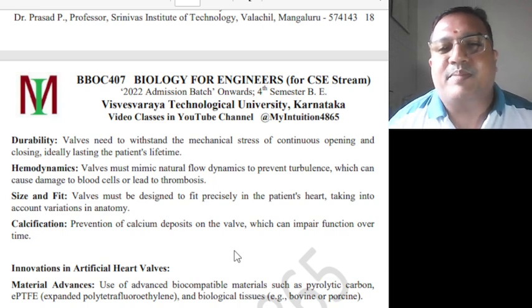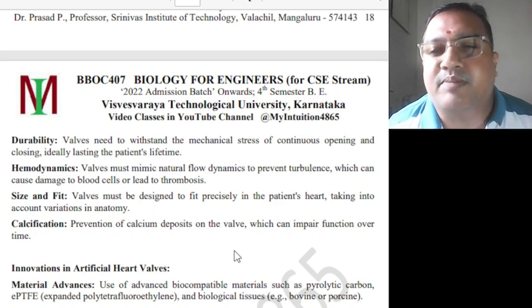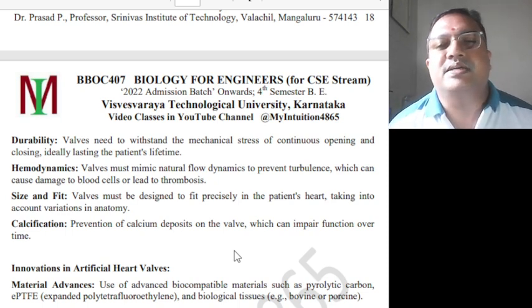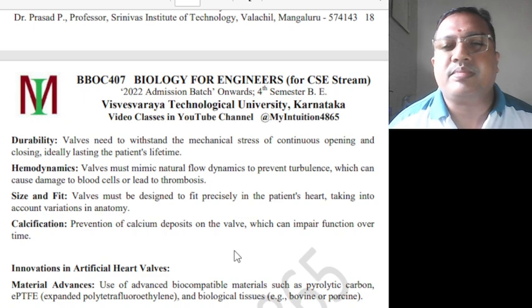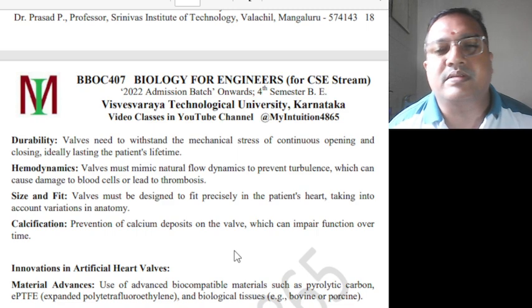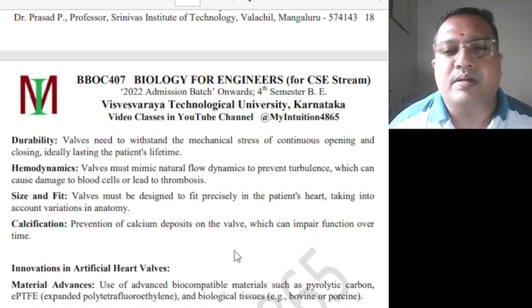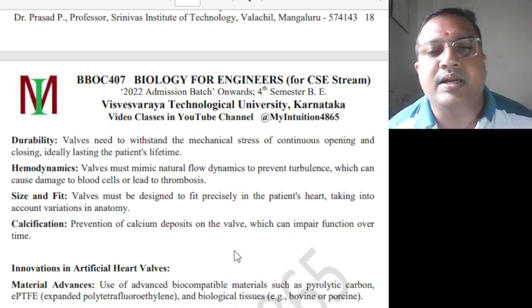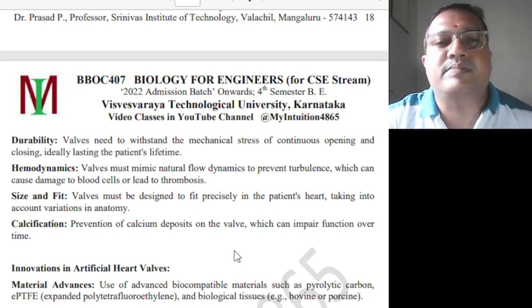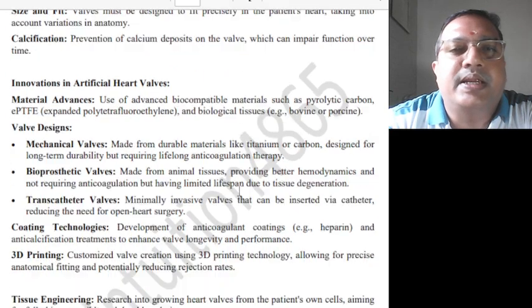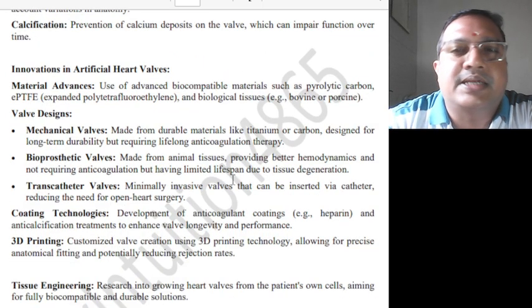Valves must mimic natural flow dynamics to prevent turbulence, which can cause damage to blood cells or lead to thrombosis. Size and fit: valves must be designed to fit precisely in the patient's heart, taking into account variations in anatomy. Prevention of calcium deposition on the valve, which can impair function over time, because our blood contains calcium also. The calcium should not deposit on that and create unwanted reactions.